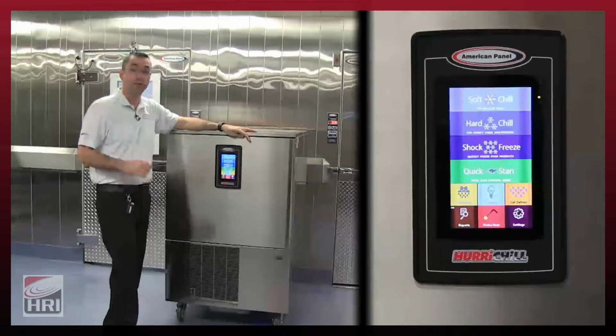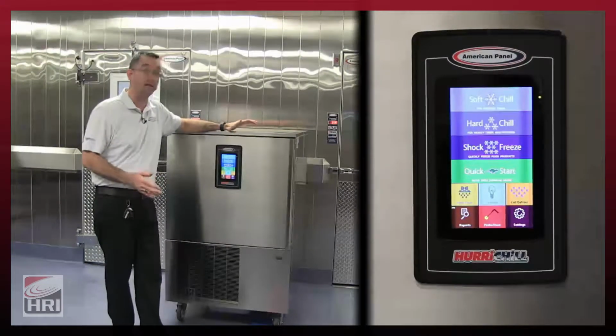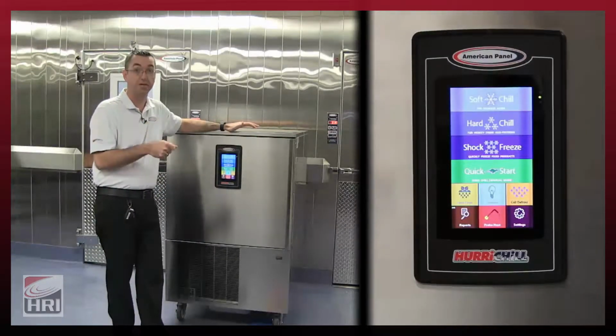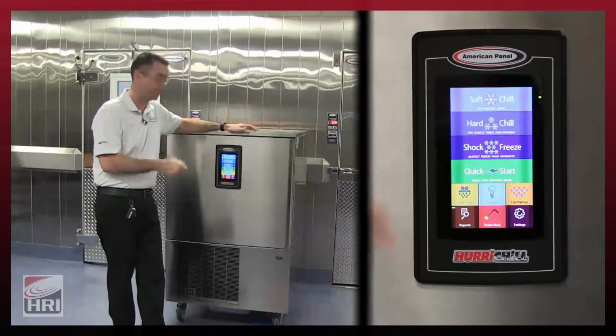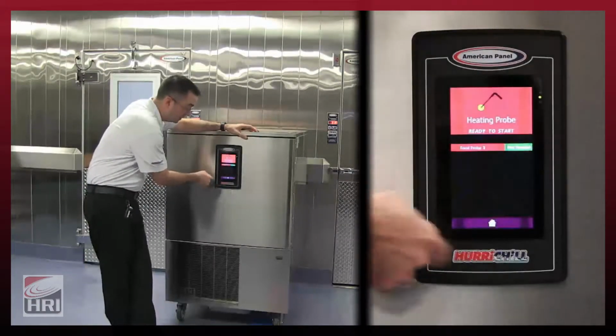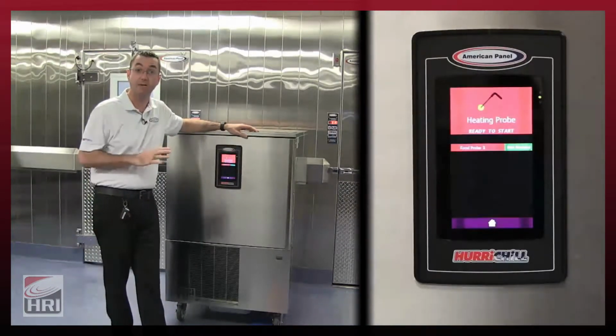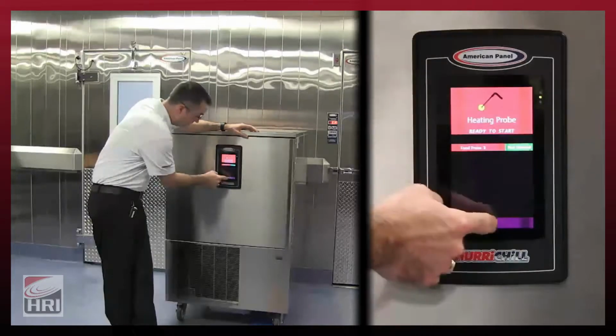Probe heat. If I'm running a shock freeze cycle, at the end of that cycle, obviously that probe is more than likely going to be stuck in that product. If I push probe heat, it's going to come on, it's going to run for 5 to 10 seconds, heat the tip of that probe, and allow me to pull it out of the food product.